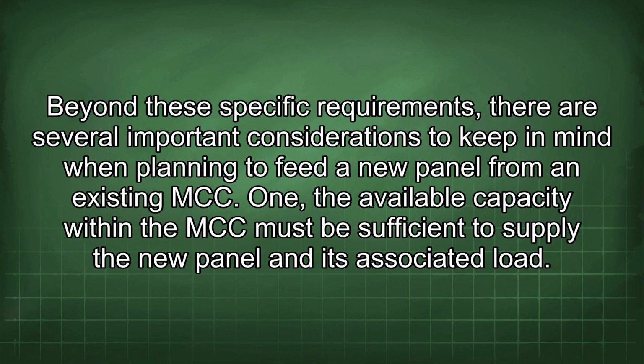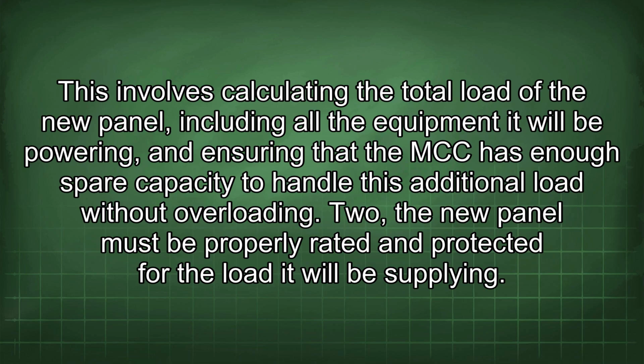Beyond these specific requirements, there are several important considerations to keep in mind when planning to feed a new panel from an existing MCC. 1. The available capacity within the MCC must be sufficient to supply the new panel and its associated load. This involves calculating the total load of the new panel, including all the equipment it will be powering, and ensuring that the MCC has enough spare capacity to handle this additional load without overloading.